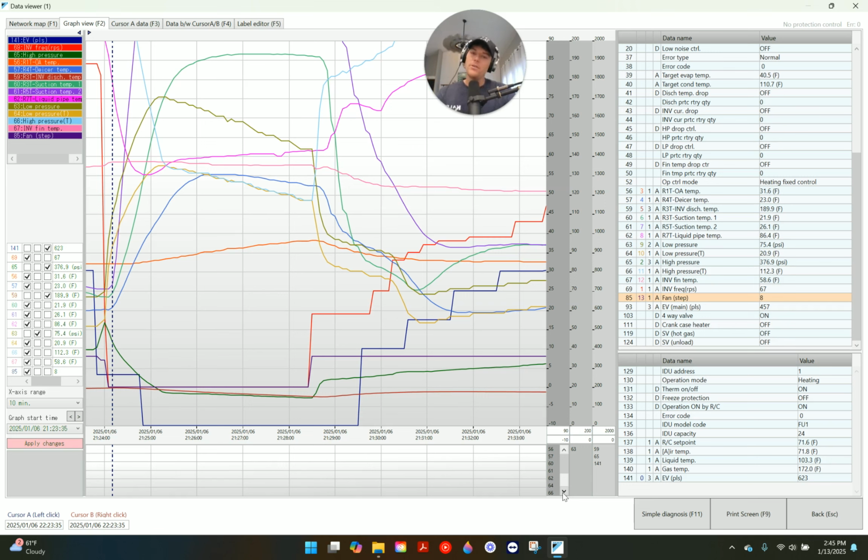And so we always follow the flow of refrigerant. And I love to start at the compressor because the compressor tells you a lot. There's that suction superheat, that discharge superheat, and that subcooling, which we didn't even get into on this data set because I'm trying to keep this video somewhat short. But again, this is how you find those problems. You think about what information do I need in that process?